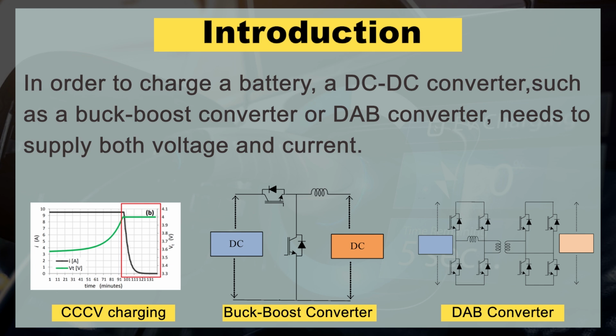One of the converters operates as an inverter unit, while the other operates as a rectifier, depending on which converter is operating as an inverter and which as a rectifier. This depends on the power flow from input to output, that is, from the DC bus to the battery, as well as from the battery back to the DC bus.